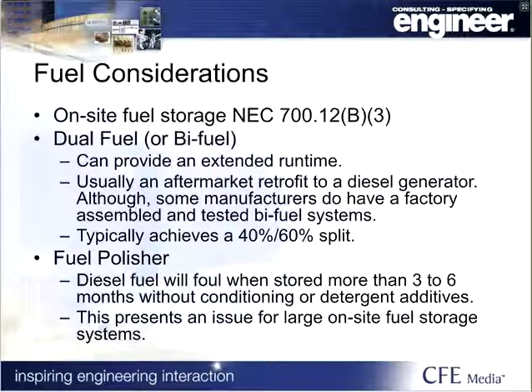Most generator manufacturer representatives can recommend a dual fuel kit manufacturer with experience on their generators. It is important to still maintain enough on-site diesel to maintain the minimum runtime for the code-required systems and shed the optional loads upon loss of the public utility gas. If you do have a large diesel oil storage system on site, steps should be taken to minimize the possibility of spoilage. Diesel fuel will foul when stored untreated for more than 3 to 6 months. Either the fuel will need to be pumped out and replaced on a certain interval or treated with additives. A fuel polisher system is a convenient way to remove water and contamination from the stored fuel.